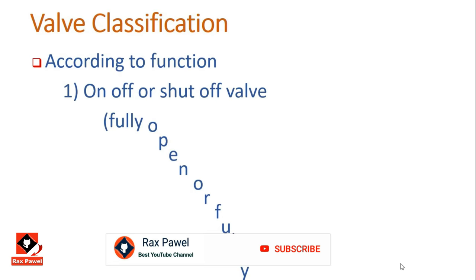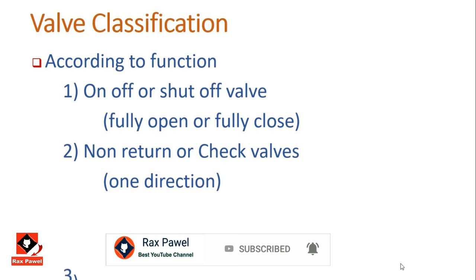Valve classification can be done in two ways. The first is according to function — how the valve affects the process or changes the flowing fluid. Here we have on/off or shut-off valves, which allow flow by fully opening or stop flow by fully closing. Then non-return valves or check valves, which allow flow in only one direction. And finally, pressure regulating or control valves, used to control the flow.